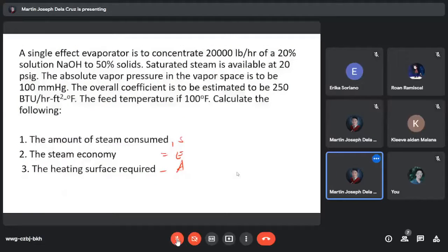So, next, di ba tatlo yung hinanap? Next is your steam economy. So, what is our steam economy class? E is equal to your vapor over steam po, vapor over steam. So, vapor natin is around 12,000 over 15,375. So, ano answer nito dito, class? 0.78.